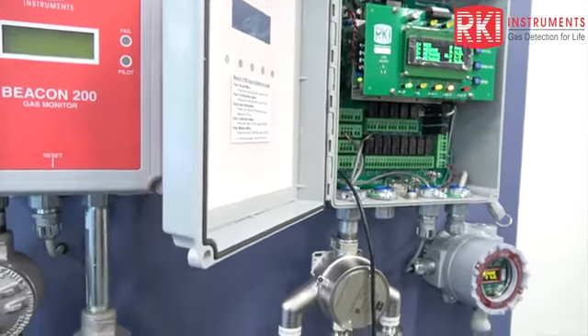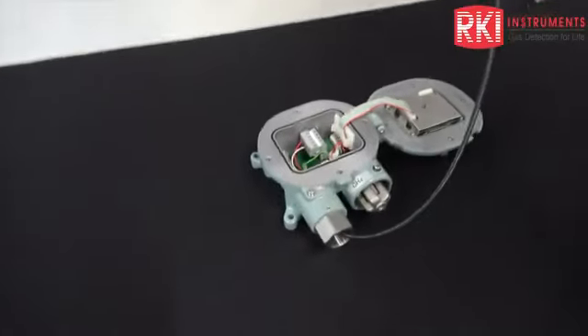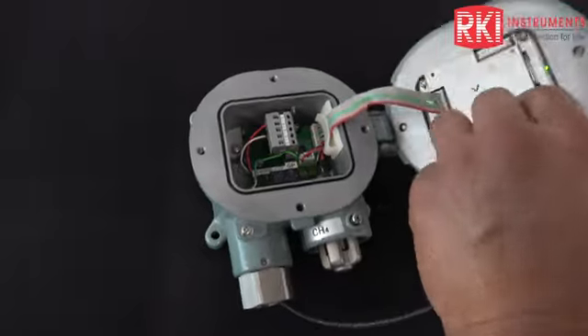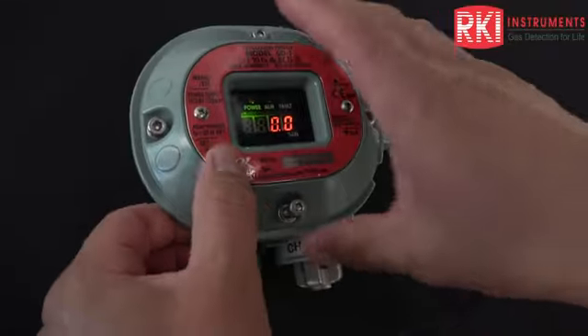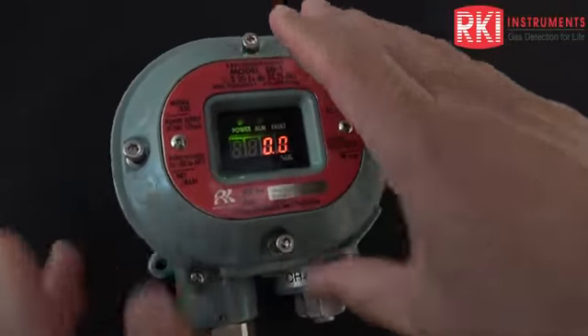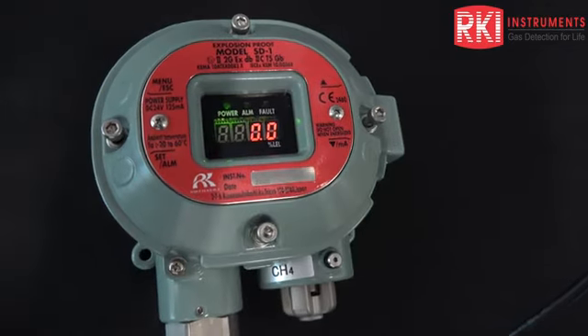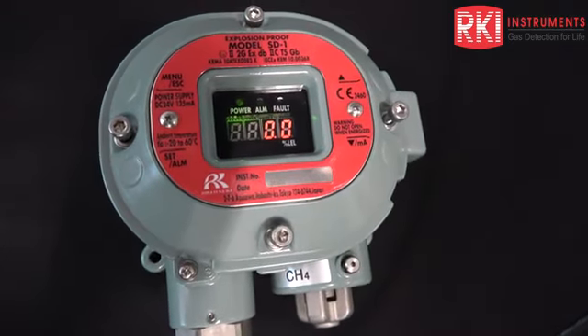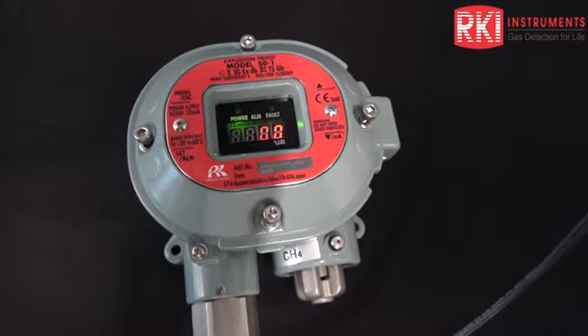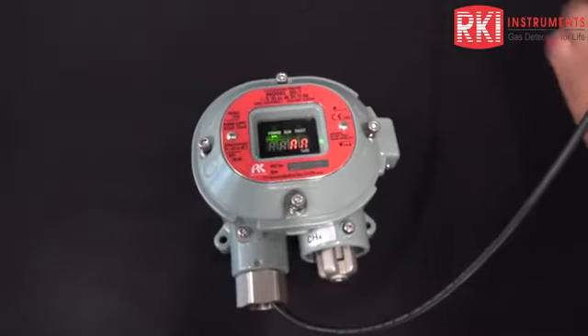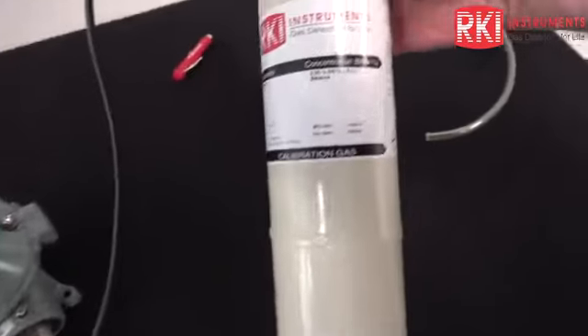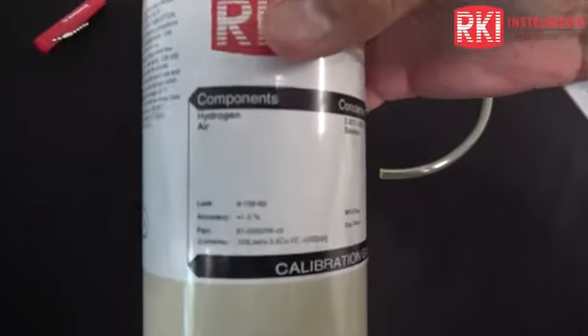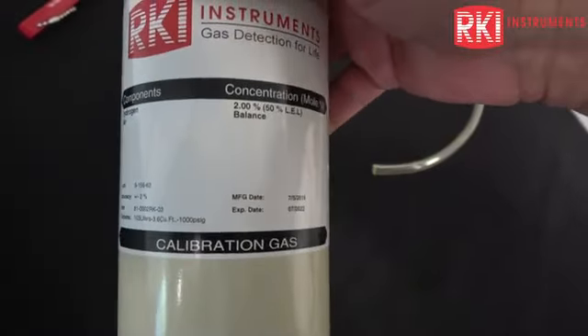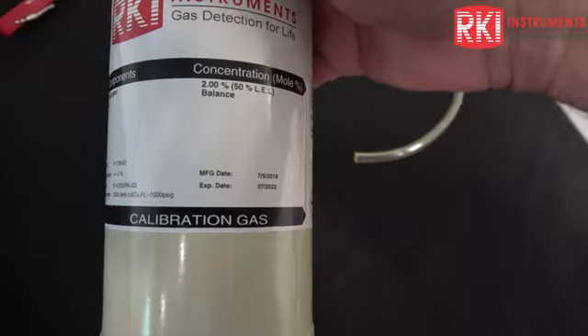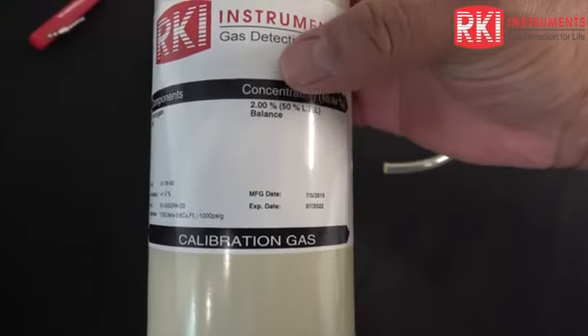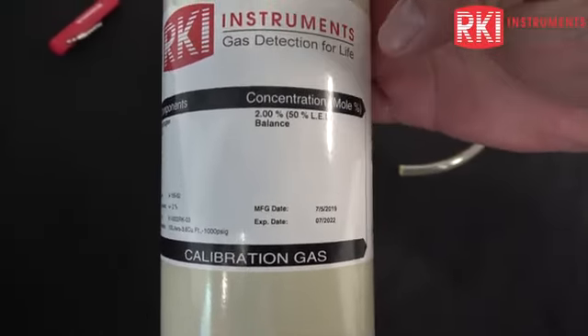Okay, so next we're going to cover a calibration procedure for this. And even though I'm using the LEL range for hydrogen, as I mentioned, I'll make some comments regarding benzene calibrations. So basically, the items that we have here are a calibration cylinder. This one is 50% LEL hydrogen in a balance of air. 2% by volume would be equal to 50% LEL for hydrogen.